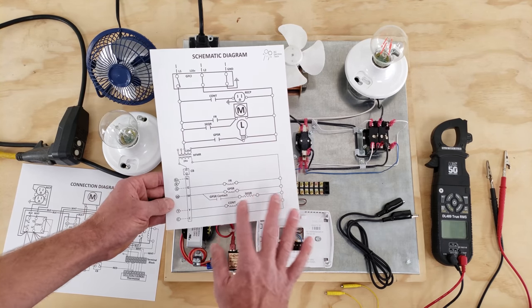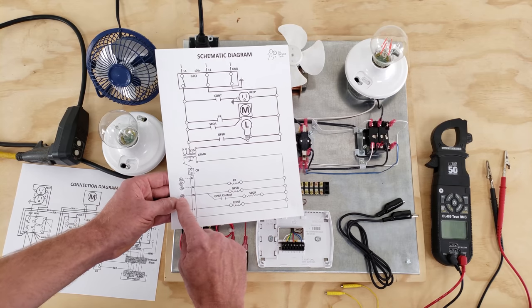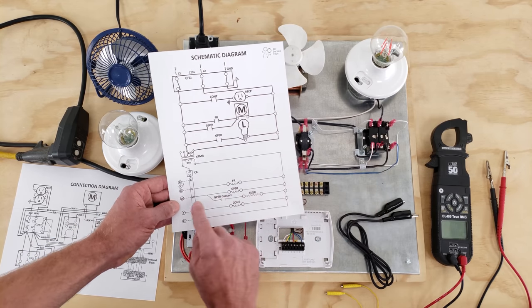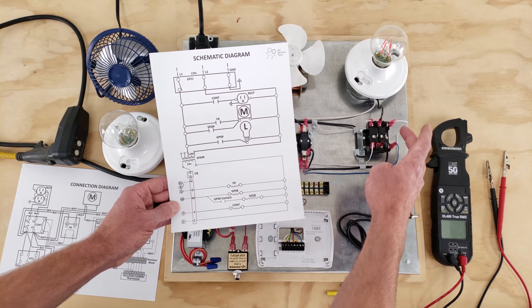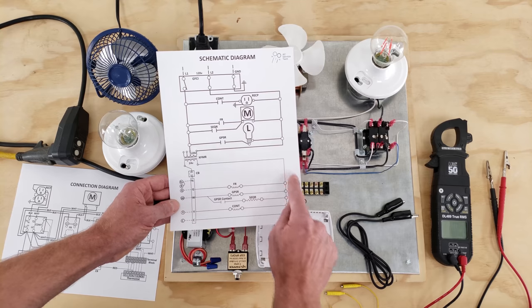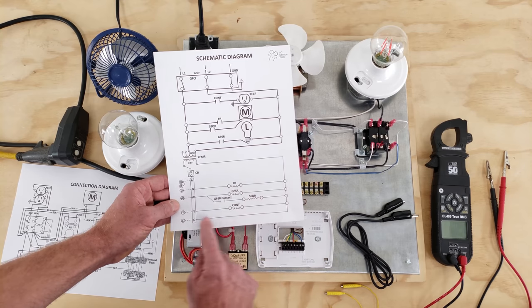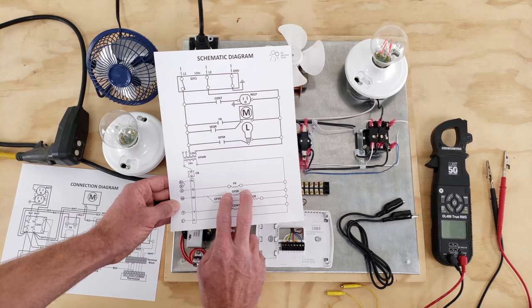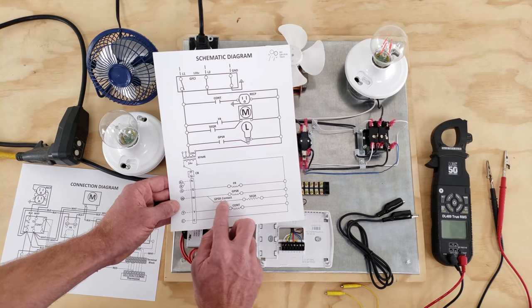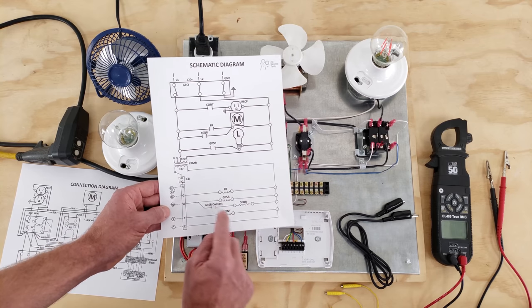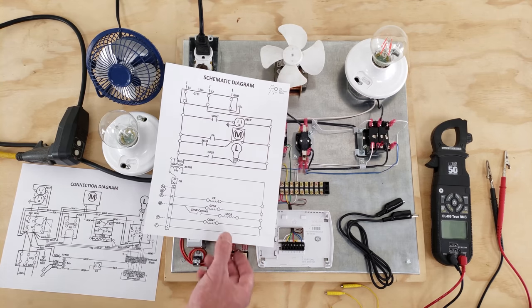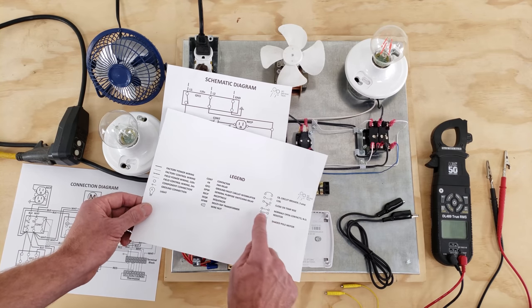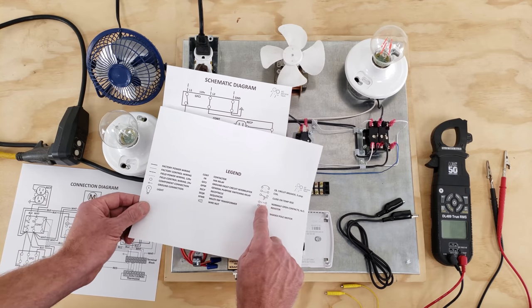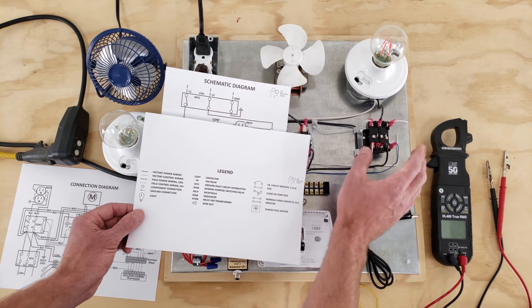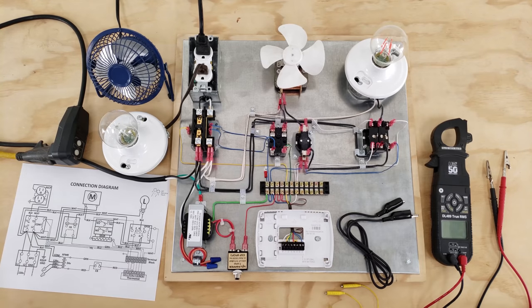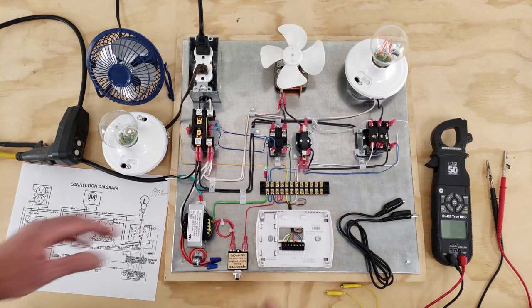And so this is just simply showing you how this operates. And over here, your GPSR, you have to power with your white wire right here over on the coil. And then you have your common over on this side. So that's going to complete the electrical circuit. And when you power this coil, your GPSR contacts, the normally open set of contacts, those are going to close. And if you don't know what those are, once again, you refer to your legend. So right here, you have your normally open contacts. Normally open contacts are closed when this relay is powered. So anyway, that's how you read a wiring diagram.